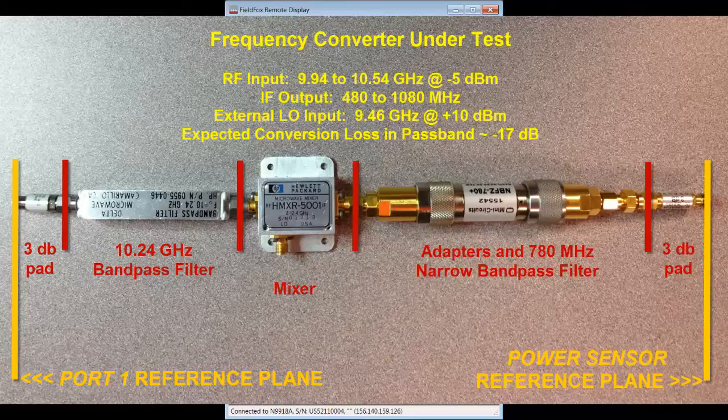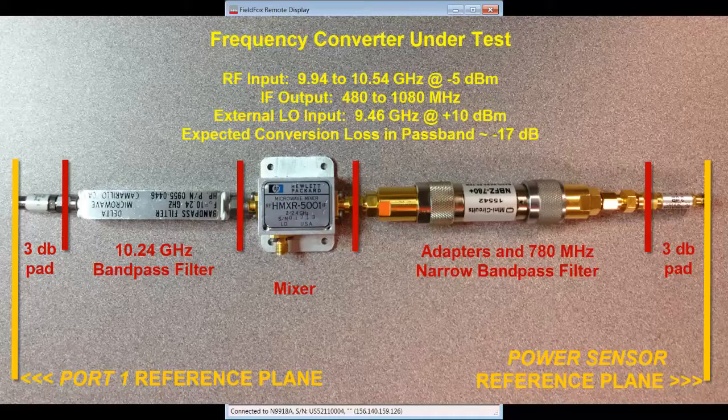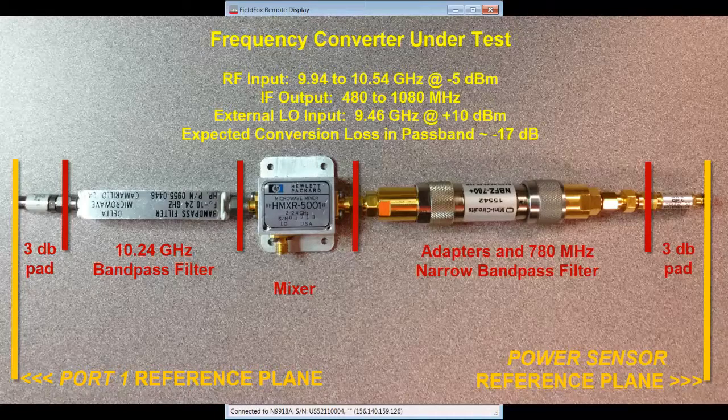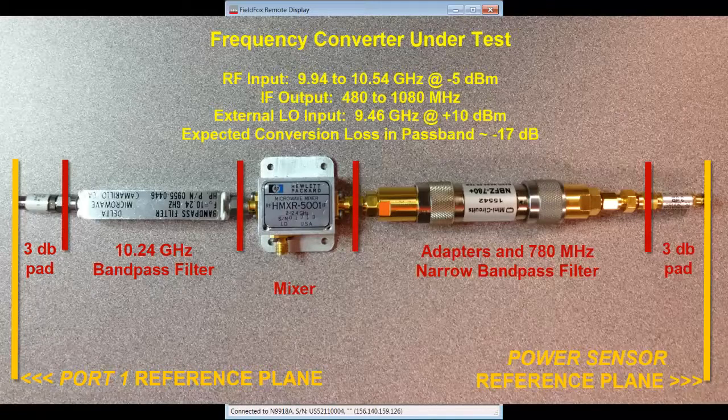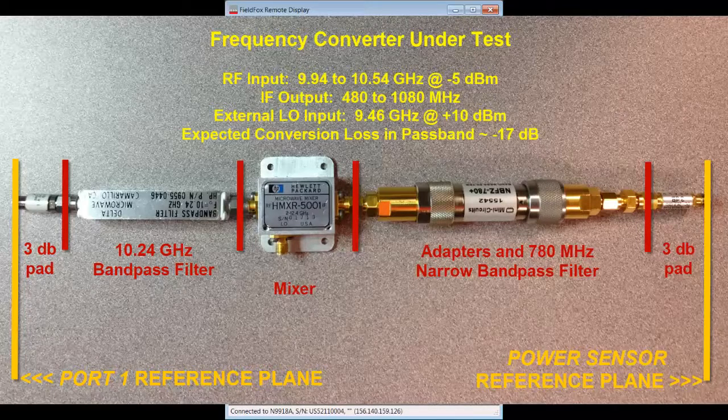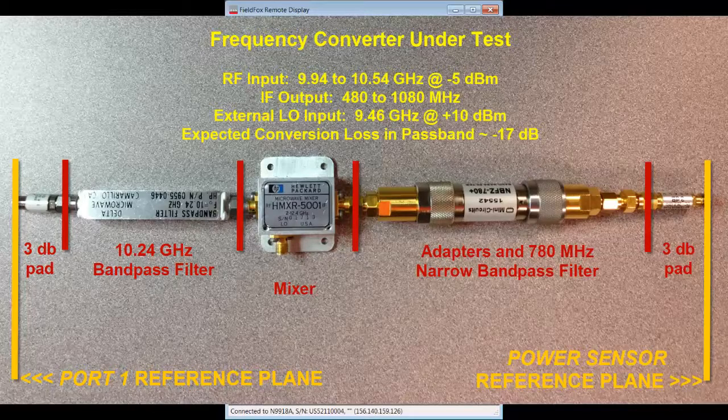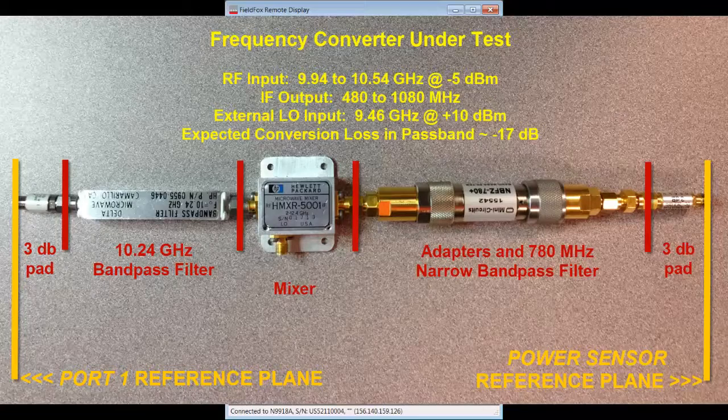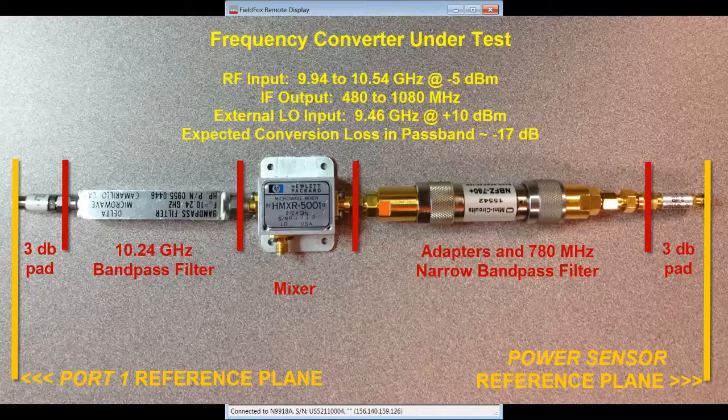The microwave radio frequency, or RF, input port will be stimulated with a minus 5 dBm signal at a center frequency of 10.24 GHz over a 600 MHz span.